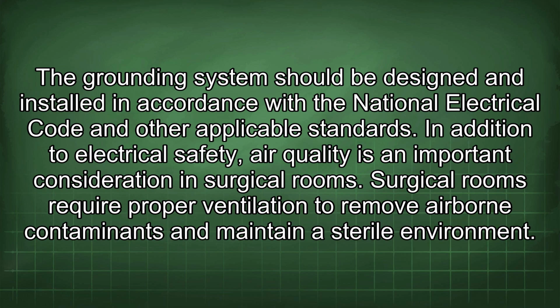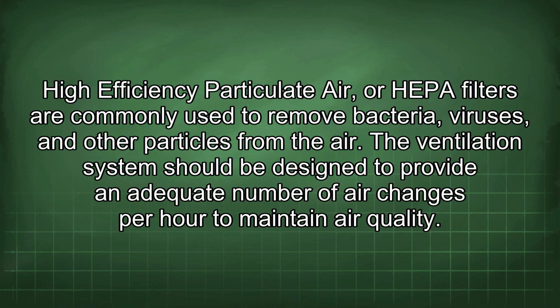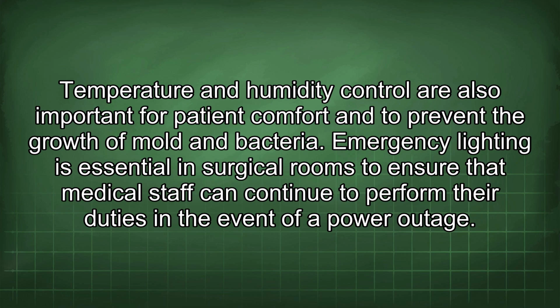Surgical rooms require proper ventilation to remove airborne contaminants and maintain a sterile environment. High-efficiency particulate air, or HEPA filters, are commonly used to remove bacteria, viruses, and other particles from the air. The ventilation system should be designed to provide an adequate number of air changes per hour to maintain air quality. Temperature and humidity control are also important for patient comfort and to prevent the growth of mold and bacteria.